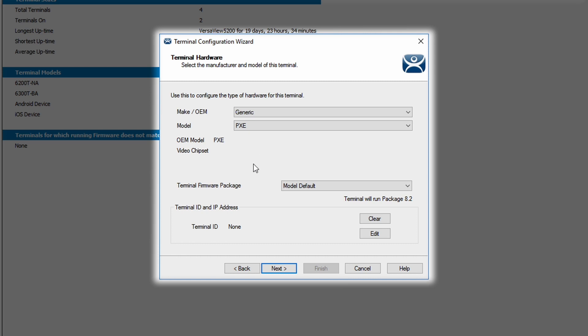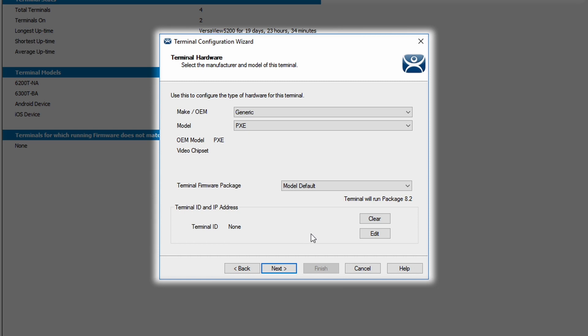I can select a terminal firmware package to be assigned to this terminal, but that's a more advanced setting that we'll be discussing in later videos. The terminal ID is simply the MAC address of the hardware that's going to be connected to ThinManager. Once the newly configured hardware is connected and booted into the ThinManager system, the MAC address will appear here and stay attached to the terminal until it's cleared by the administrator. If you have that MAC address information prior to installing your hardware, you can hit the Edit button and add that MAC address manually, which may save you a few seconds of boot time.